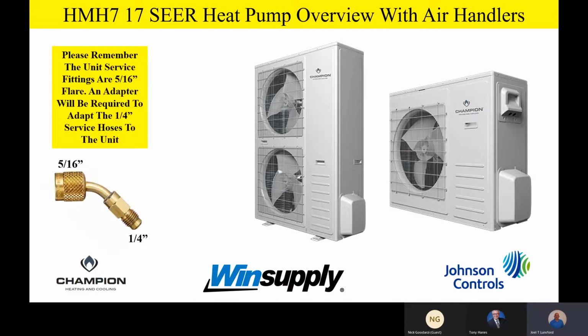Now, as a fast reminder also, we need to remember that the service unit fittings themselves, where you hook your service gauges, are a 5/16 flare. And so we're going to need some of these adapters. Contractors are going to want to make sure they have these adapters on their truck so they can go from that 5/16 flare down to a 1/4 inch service hose flare fitting. As you take a look at that adapter, it's 5/16 on the female end, 1/4 inch male on the other for your service hoses.